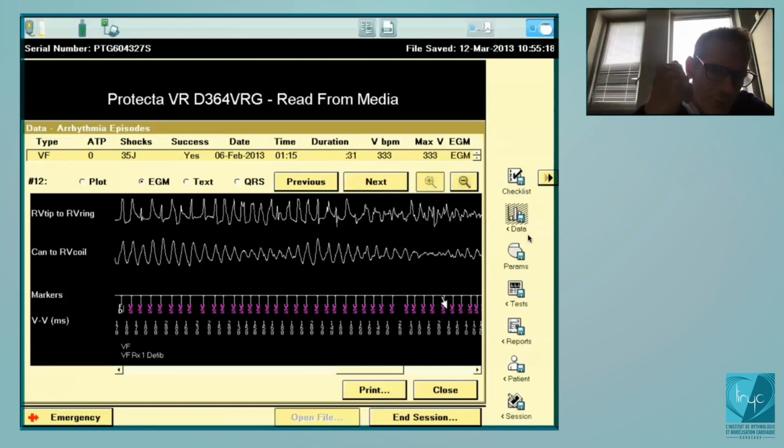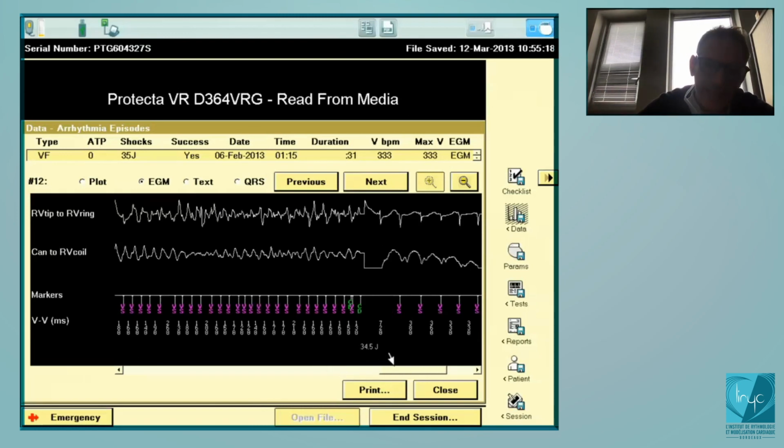That's an old version. It was like this in the very first version of the defibrillators, because in the very first version, once the defibrillator started the charge of the capacitors, there was no analysis about whether you are fast or not. Whatever, in these old devices, you will go up to the end of the charge and then decide if you will shock or not. Okay, so that's why they were labeled VS, but it's the same now in the new ones. It's always labeled VS once you charge the capacitors.